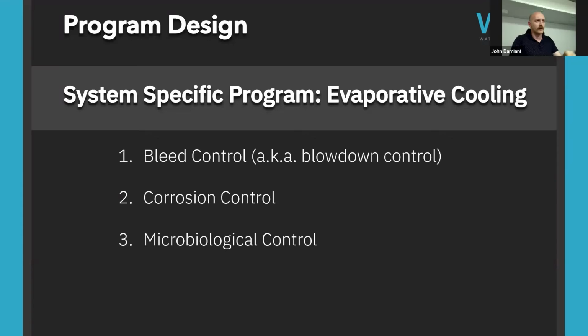Okay, so digging in one more level, system specific, the program for evaporative cooling. Well, there's really only 3 things that we're doing. All of those objectives are really addressed by just these 3 things. So number 1 is bleed control, also known as blowdown. If you're more familiar with steam systems, blowdown will be the same term. You can use them interchangeably. So bleed control is a mechanical method of keeping the cycles of concentration under control. Second is corrosion control. So we want to minimize corrosion, so we're not rotting out the system and causing premature failure. And then microbiological control. So scale and corrosion control actually should be both in there, but the bleed control actually addresses the scale control as well.